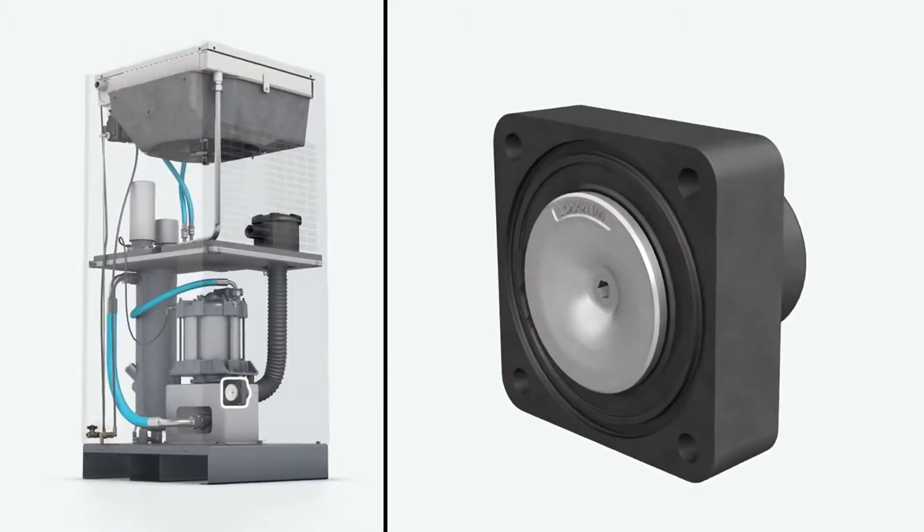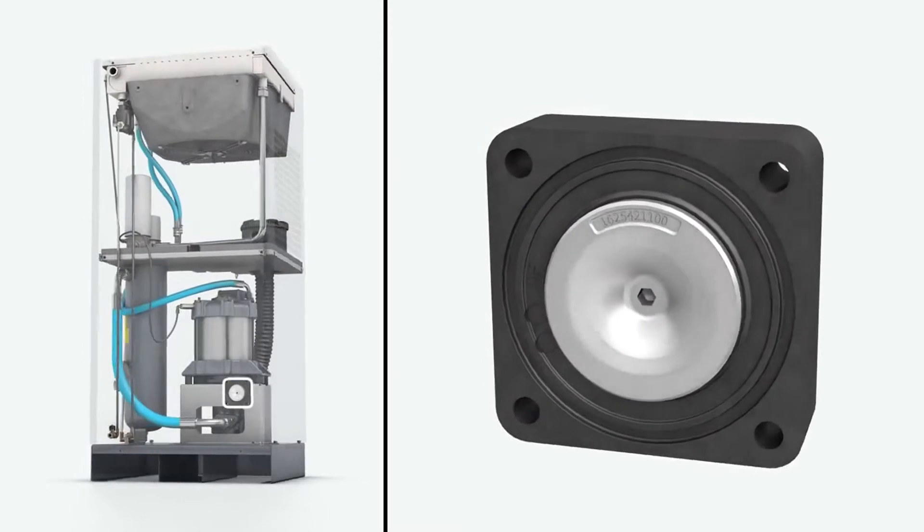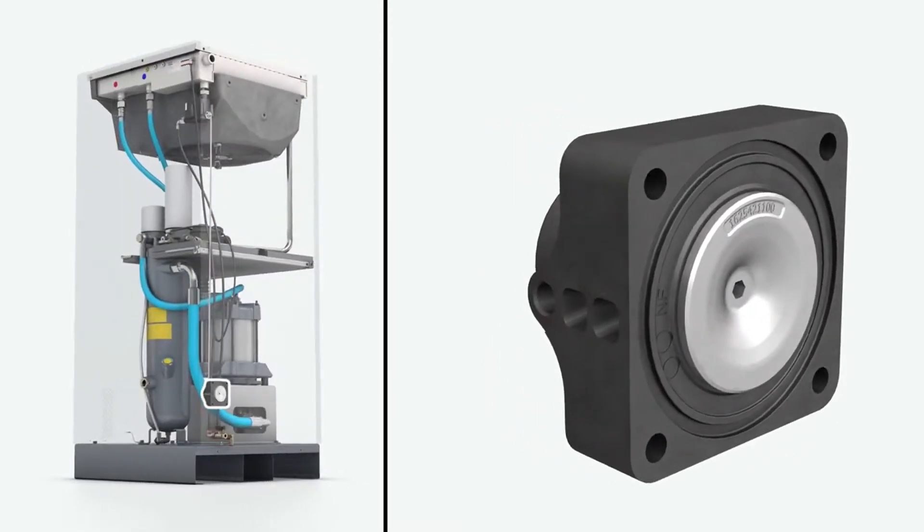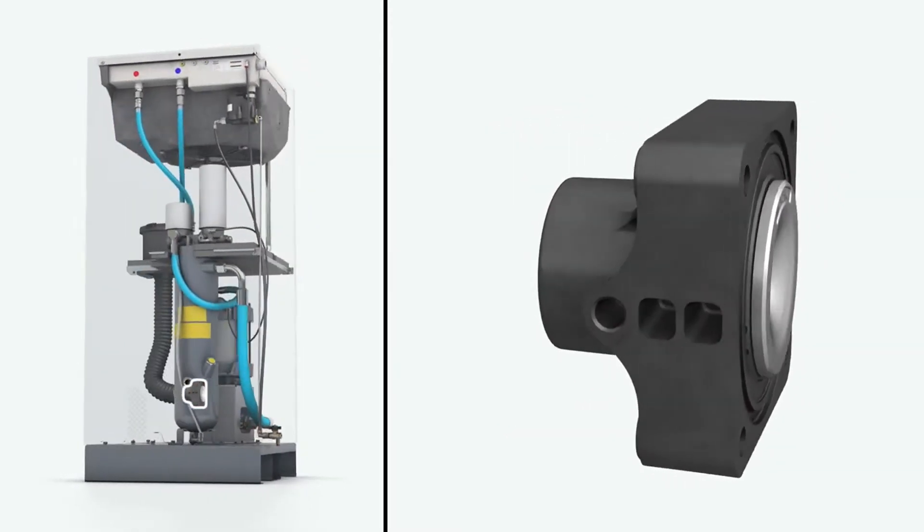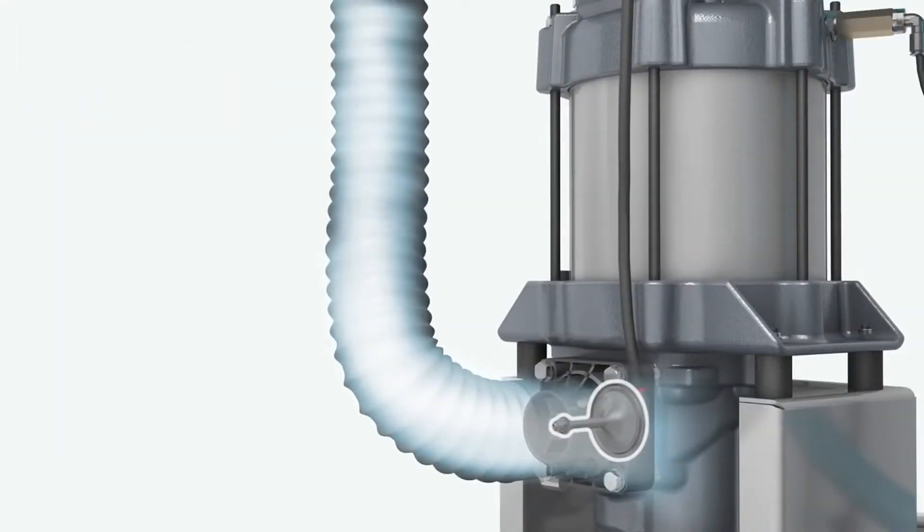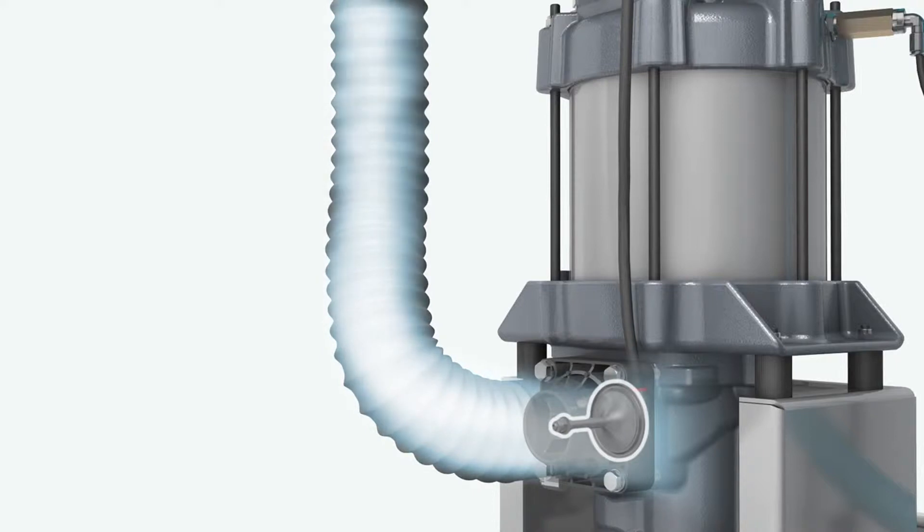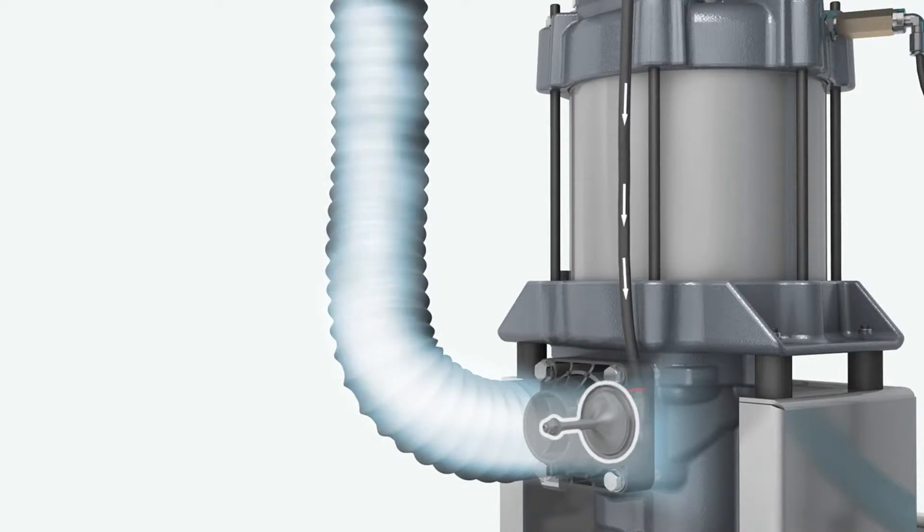This small air inlet valve is regulated by a simple fail-safe system. When air is taken in, the air inlet valve mechanically opens. When no air is needed, a solenoid detects the stop and sends a pulse of compressed air to the valve to close it again.